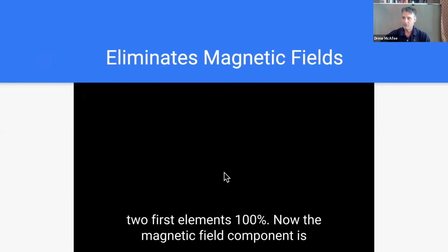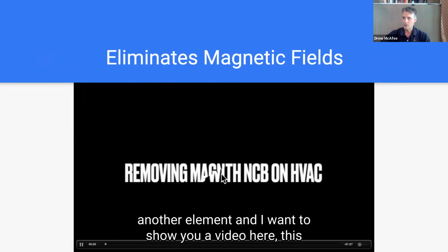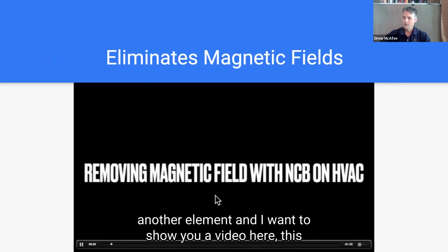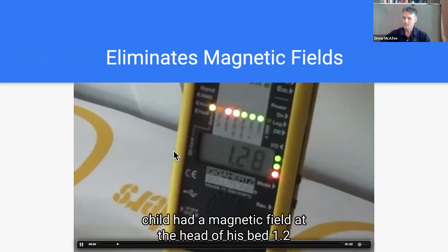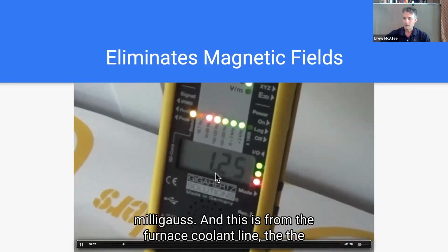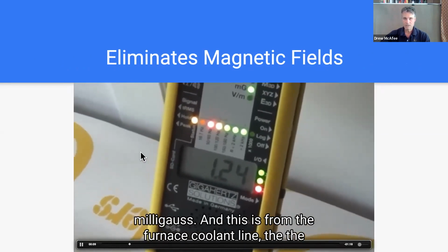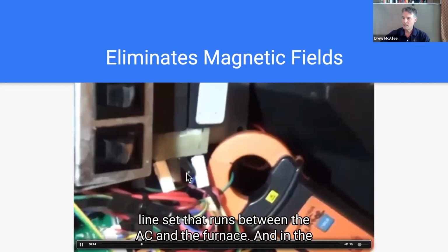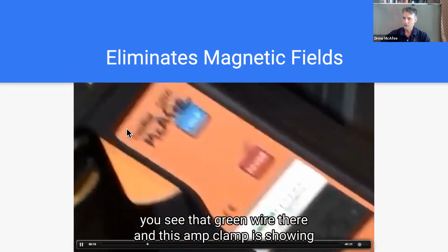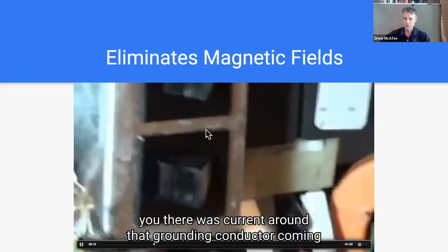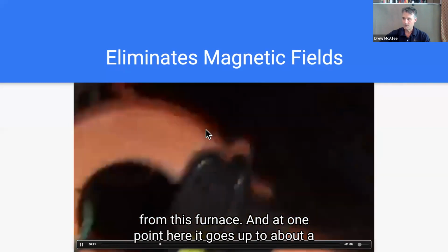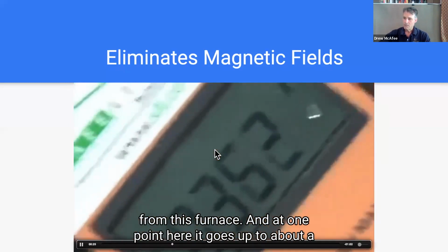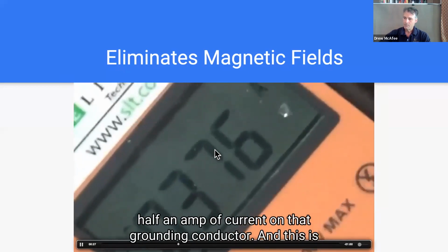Now, the magnetic field component is another element, and I want to show you a video here. This child had a magnetic field at the head of his bed, 1.2 milligauss. This is from the furnace coolant line, the line set that runs between the AC and the furnace. You see that green wire there, and this amp clamp is showing there was current around that grounding conductor coming from this furnace. At one point here, it goes up to about a half an amp of current on that grounding conductor.